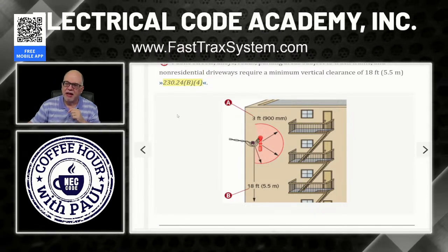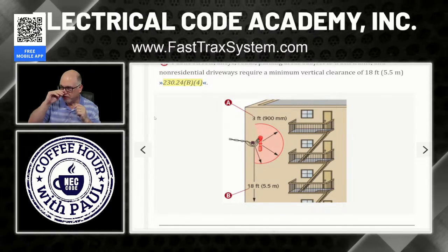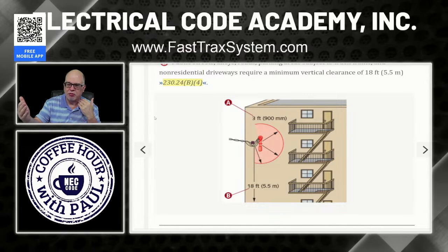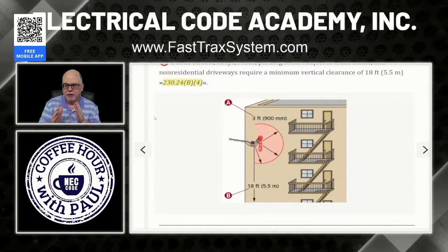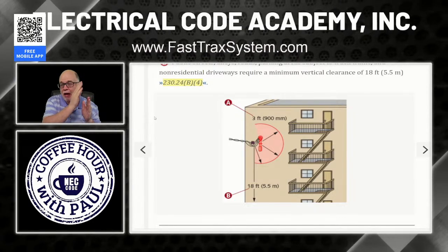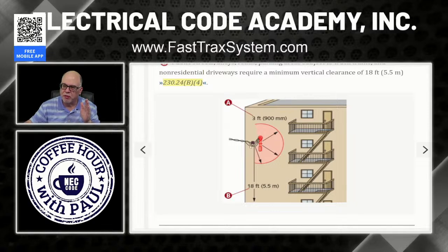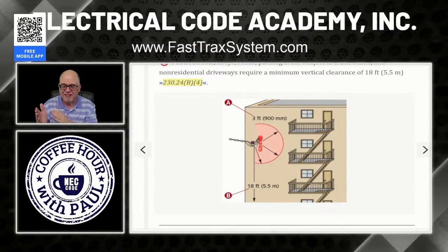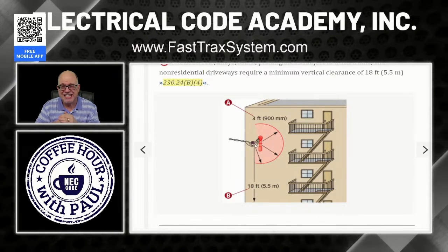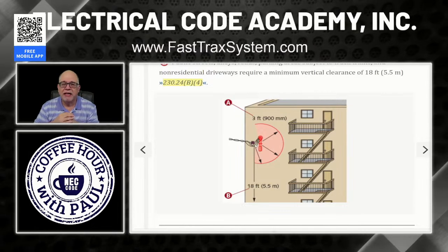However, let's say this property had a transformer that was 50 feet away, and the utility said, we're going to stop at this transformer. Yet it's too far for the service drop to go over to the actual building, so they have to put another pole in. Now, if they stop at the transformer, that is now the service point. And the drop from that transformer to the pole, and in continuation from that pole to the side of this building, might be installed by the electrician. And if that's the case, that is called overhead service conductors. And that is indeed governed by the National Electrical Code. In fact, that is what we're talking about here in 230.24.